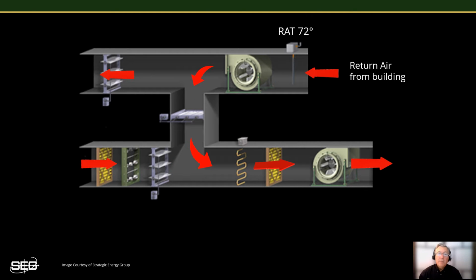Now, let's go a little deeper. In this example, the temperature of the air returning from the zones, denoted here as RAT for return air temperature, is 72 degrees. The outside air temperature, denoted as OAT, over on the left side of the screen, is showing that it's 35 degrees. And the outside air damper is at 45% open, and it's controlling how much cool outside air is being drawn in. The combining of the cool outside air and the warm return air results in a mixed air temperature of 55 degrees. Currently, the supply air temperature set point is also a constant 55 degrees.